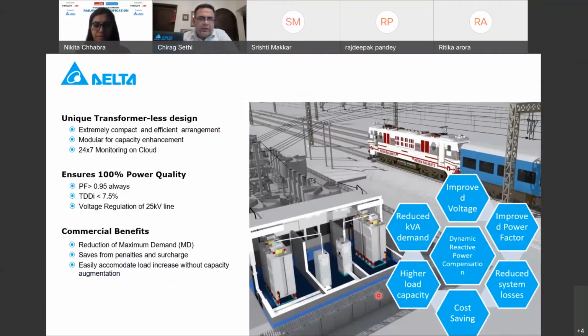What is unique in our product is that it is a solution rated for 25 kV traction voltage, which implies that we do not need an additional step-up transformer to connect it to the 25 kV. The modules are connected in series, whereby a rating of up to 52 kV insulation class is met. So we can directly connect it to the 25 kV feeder. It is modular in nature.